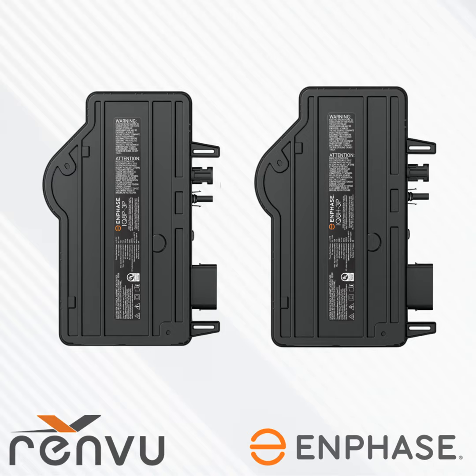particular cabling. Now, voltage rise is a concern when you're dealing with conductor runs as long as our QD cable. And Enphase recommends you keep that voltage rise at less than 2%. So all of our cabling options include a center tap connector intended to mitigate problems that may arise due to that voltage rise issue. You'll find there's a center tap connector after every 6 drops, and you should wire those center tap connectors into a center tap adapter, and then from your center tap adapter is a home run to a sub panel somewhere.